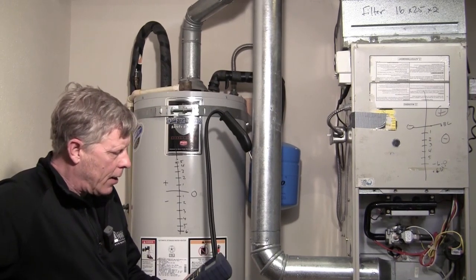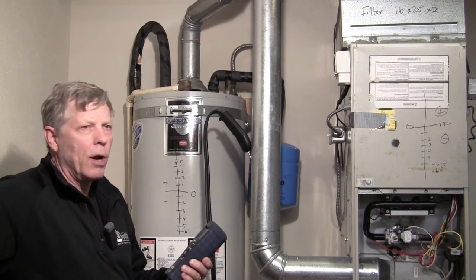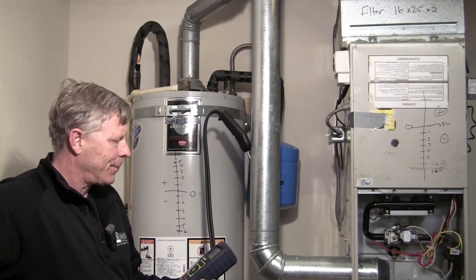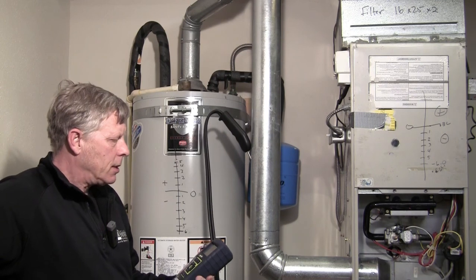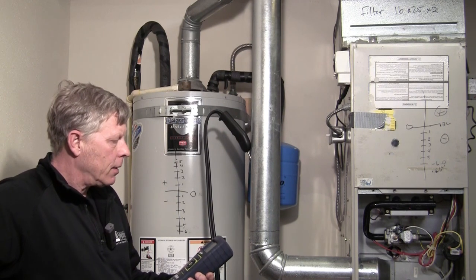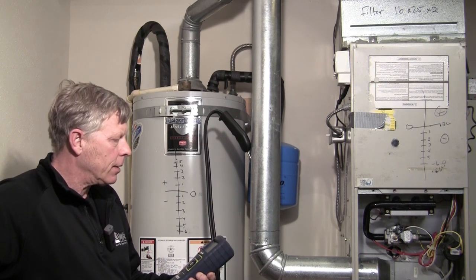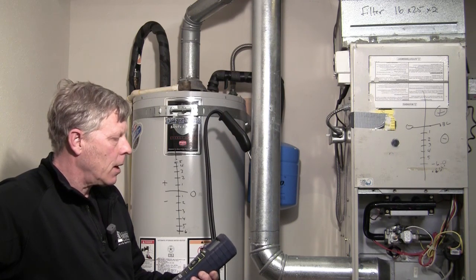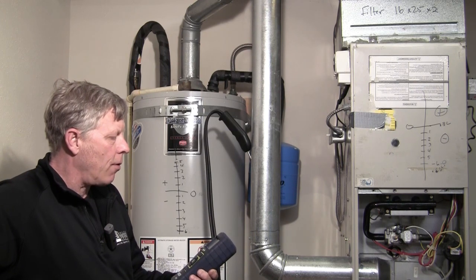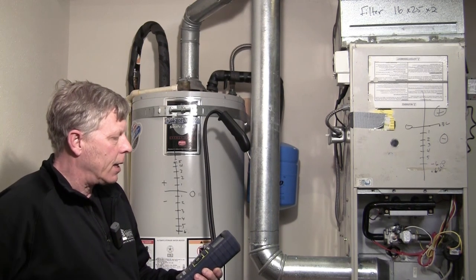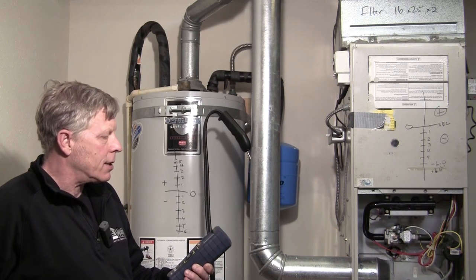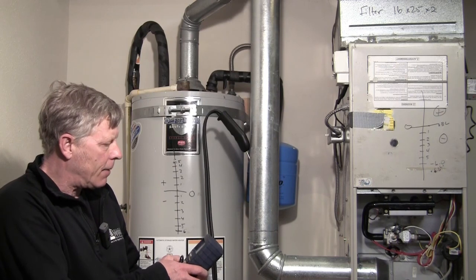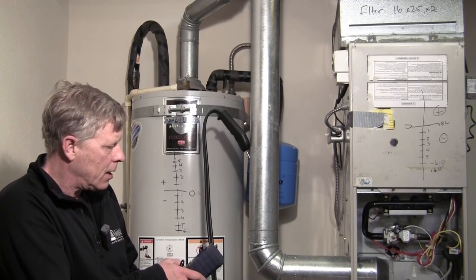Okay, it's up around 100. This is allowed to be 400 parts per million air free according to the standard. It's 145, 150s, 163, 164. Okay, it's kind of leveling off at about 170, 172 it looks like. I'm going to go up and check efficiency.